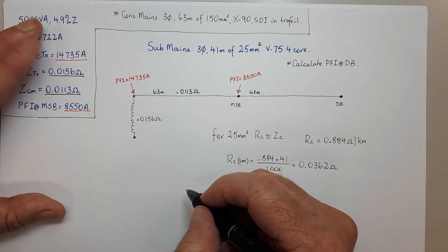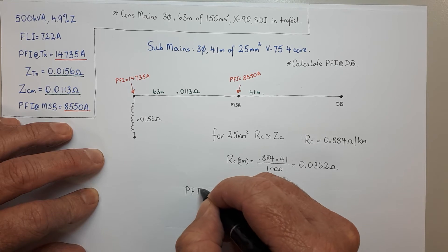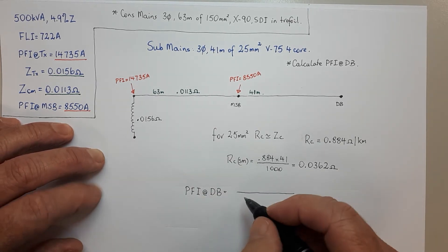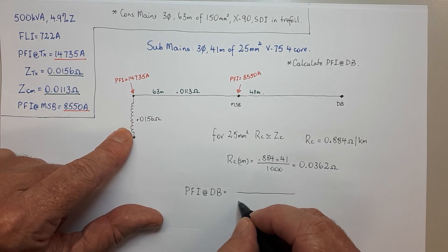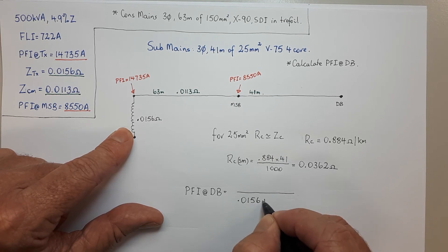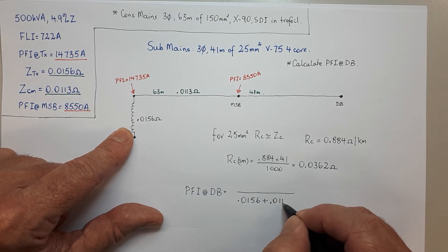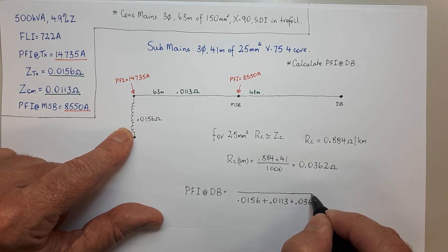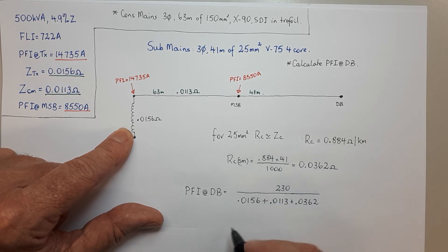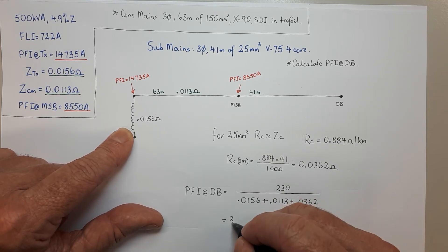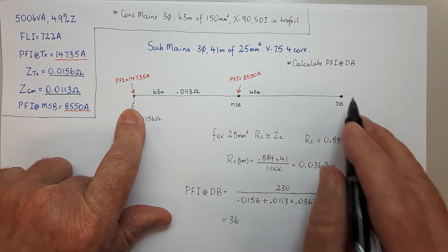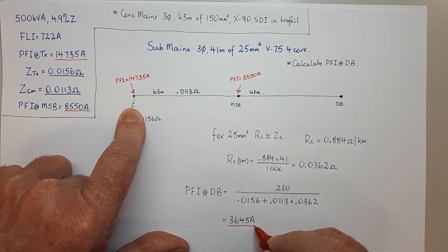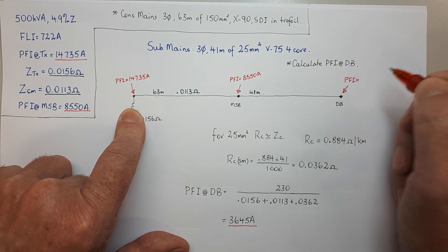So that means the prospective fault current at the distribution board is this long fraction. We've got to include the transformer — because that's going to be in the loop if there's a fault current. So we have 0.0156, plus 0.0113, plus 0.0362, giving us 230 over all of that. Probably shouldn't be too surprised it's dropped down a fair bit — from 14,700 odd at the transformer, by the time you get here it's 3,645 amps. So the PFC at the DB is 3,645 amps.